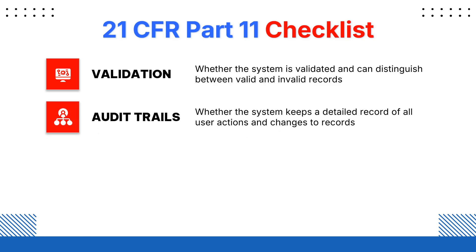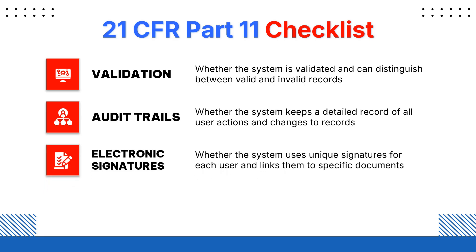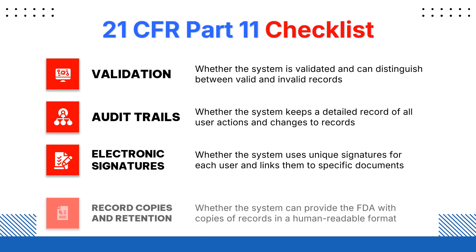Second is audit trail. Whenever a system keeps a detailed record, there are changes in the record, and each user action or change in the record needs to be verified by the audit trail — the source of the data change needs to be traced. Next is electronic signature: whenever a system uses a unique set of signatures, each user needs to have a different ID for the electronic signature, and that should be a specified link to the specified document.